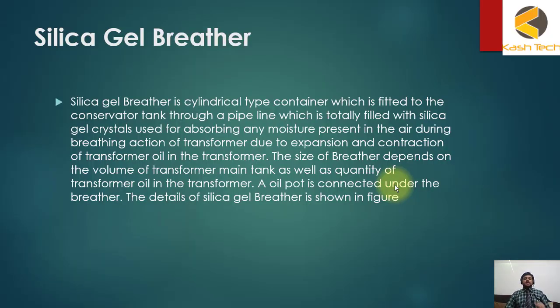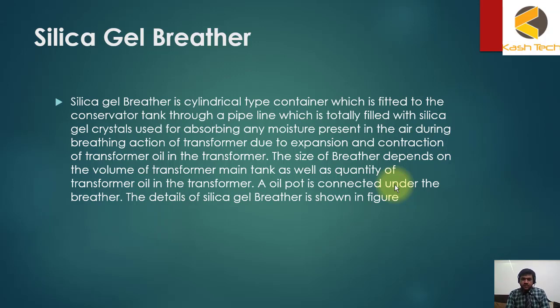Our next topic is silica gel breather. A silica gel breather is a cylindrical type of container which is fitted to the conservator tank through a pipeline, and it is totally filled with silica gel crystals used for absorbing any moisture present in the air during the breathing action of the transformer.